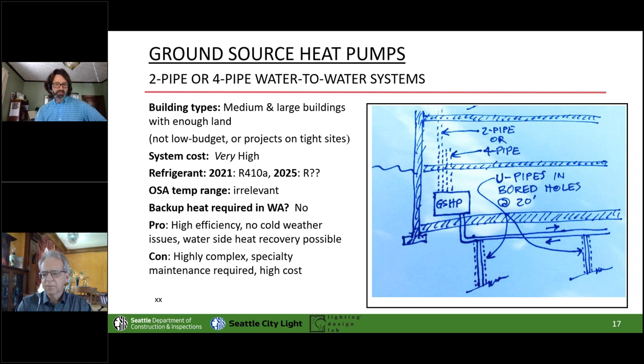And it's worth saying that there's as many ways to lay out a well field as probably well field designers. There's strong opinions on all sides of that. Don't want to wade into that. But ideally, you want the ability to say, at least by branch, I get this much flow, and balance that flow out so that you're getting roughly equal fluid flow through every branch. And other than that, there is no one right answer. It's an it depends, and designer specific desire.